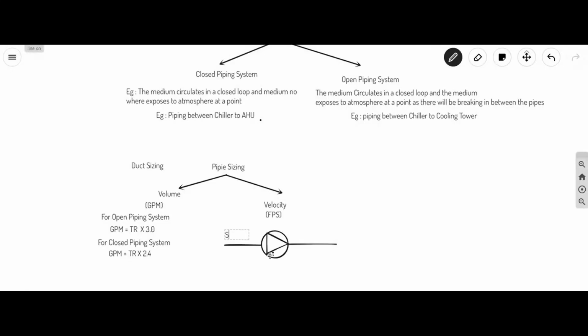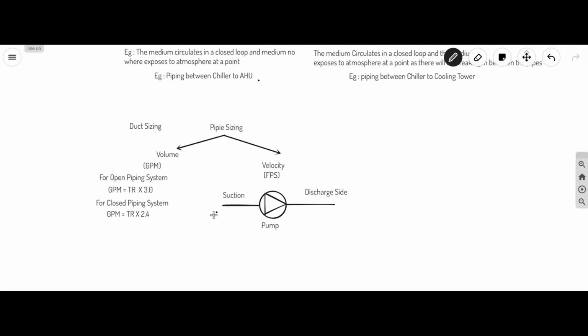This is suction side of the pump. This is pump. And this is discharge side. In the suction side of the pump, velocity will be 4 to 7 FPS. Approximately we go with 6 FPS. In discharge side, we go with 8 to 12 FPS. Approximately, we go with 10 FPS.